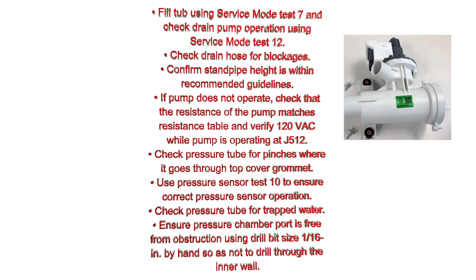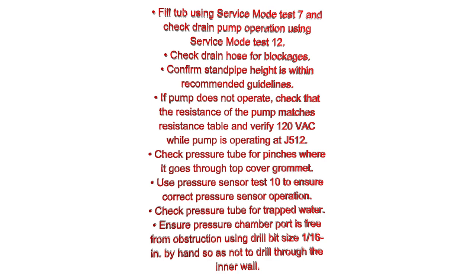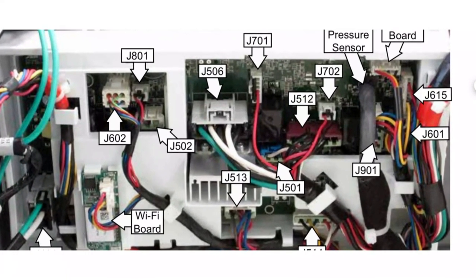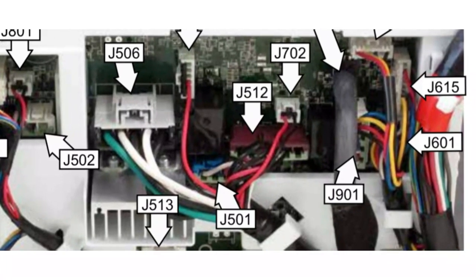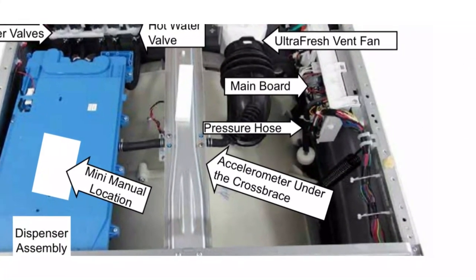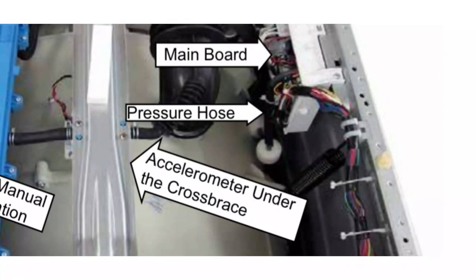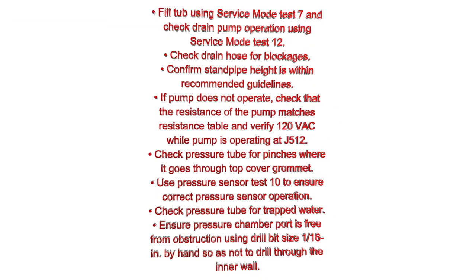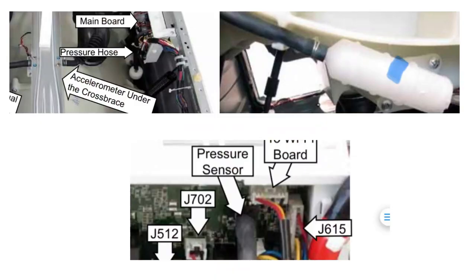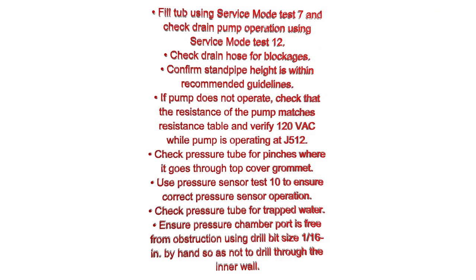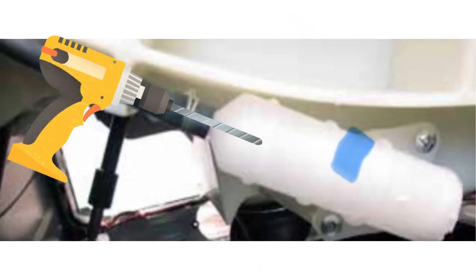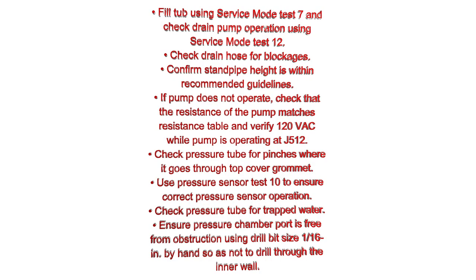If pump does not operate, check that the resistance of the pump matches resistance table and verify 120 VAC while pump is operating at J512. Check pressure tube for pinches where it goes through top cover grommet. Use pressure sensor test 10 to ensure correct pressure sensor operation. Check pressure tube for trapped water. Ensure pressure chamber port is free from obstruction using drill bit size 1/16 in by hand so as not to drill through the inner wall.